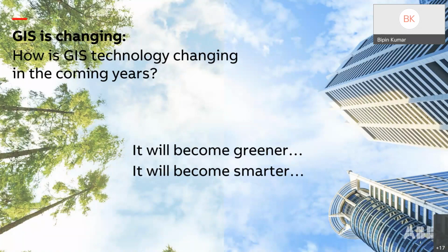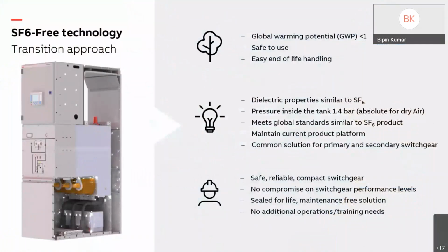As a step in that direction, this is a greener GIS, as we call it, because what we are using inside is dry air. Dry air, in very simple terms, is a mixture of oxygen and nitrogen with humidity taken out. So it is as simple as the environmental air we have used. By doing this, the global warming potential is near to nothing for this particular switchgear, and it works perfectly 100% as a normal switchgear would. If you compare it with a conventional GIS, there's no change in terms of overall life cycle and overall serviceability of the product.